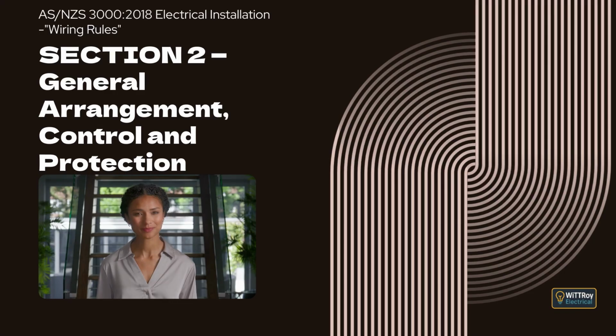It also explains that the choice of protective devices, and the way they are set, must be checked during inspection in line with Clause 8.2.2, Sub-Clause C, Item 2. Clause 2.5.7.2, Coordination of protective devices. Clause 2.5.7.2.1, General. This clause says that when we choose protective devices, we need to think about two things. One is discrimination, also known as selectivity. The other is backup, also called cascading.